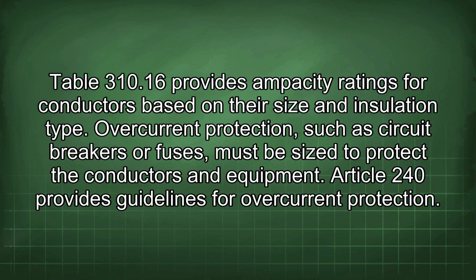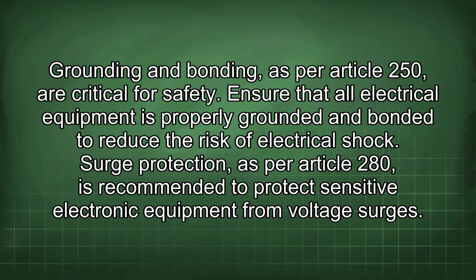Overcurrent protection, such as circuit breakers or fuses, must be sized to protect the conductors and equipment. Article 240 provides guidelines for overcurrent protection. Grounding and bonding, as per Article 250, are critical for safety. Ensure that all electrical equipment is properly grounded and bonded to reduce the risk of electrical shock.